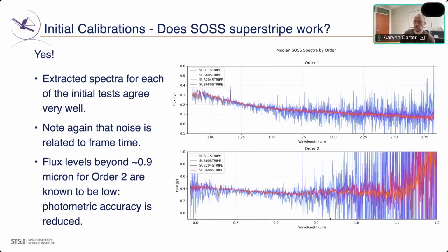It's quite a known effect for SOSS, really. The throughput and the photometric precision at those wavelengths is really quite low. So it's not unusual to get poor performance out there. And really 0.6 to 1 micron is the range where we say SOSS order 2 is best operated at. And that's nice because beyond there, you can already pick up from order 1 anyway.